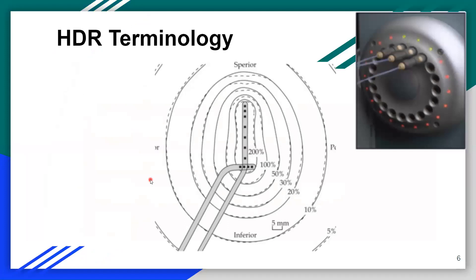If you're doing brachytherapy, some of the terminologies need to be remembered. This is a typical isodose lines of tandem and ovoid. Here you can see, these positions are called dwell positions, and certain positions the source will stay and deliver the dose. The stay time is called dwell time. This is an indexer in which the guiding tubes are connected and the source travels through these guiding tubes. Indexer numbers are quite important to remember, and the source guide tube positioning is also very important. Here you can see the effect of inverse square law, the sharp fall off of the doses.